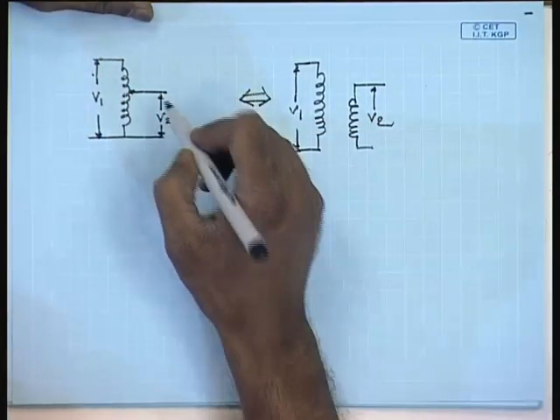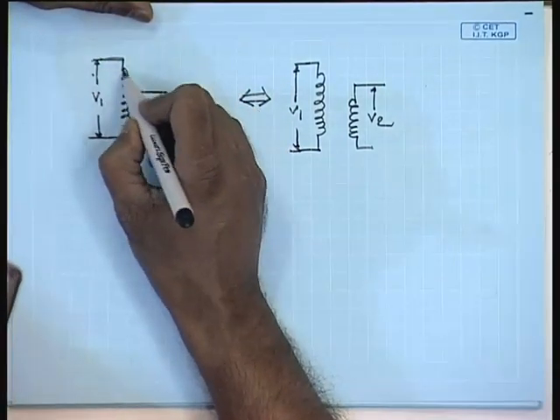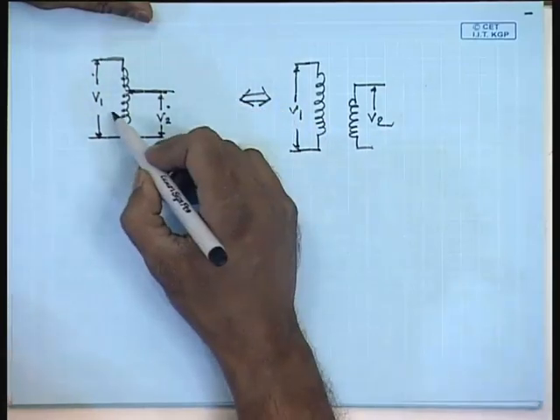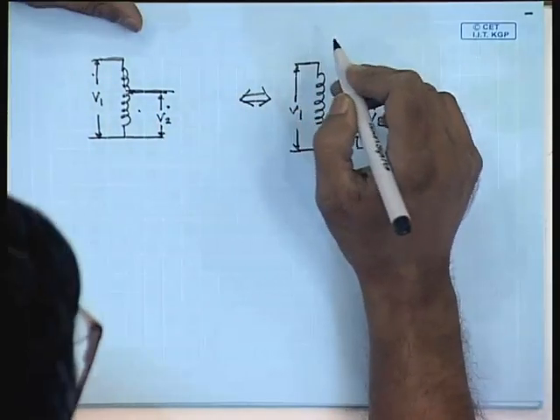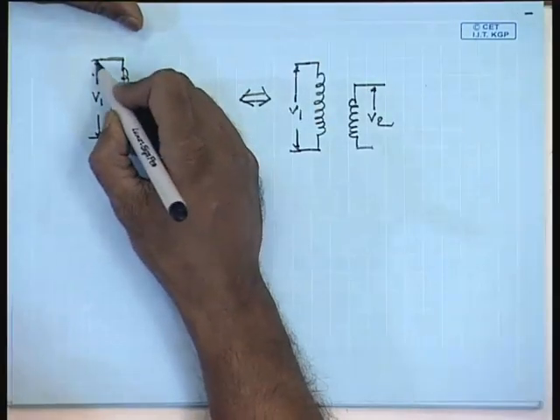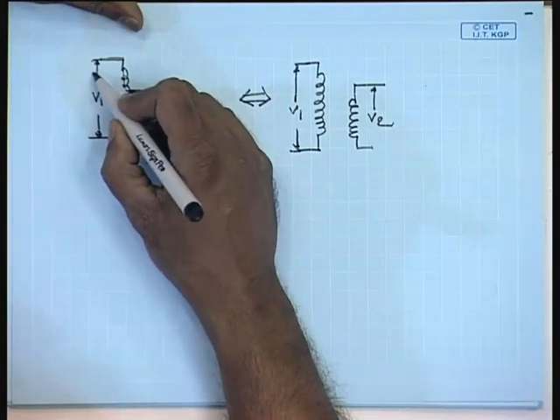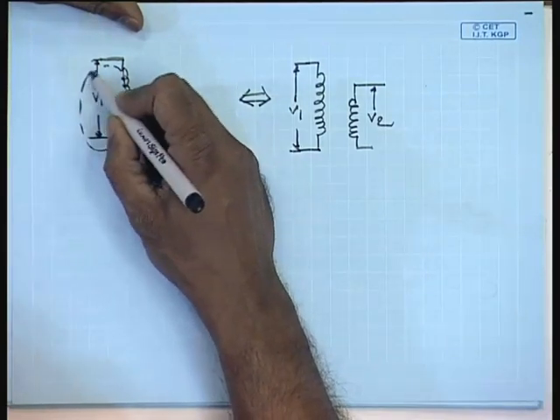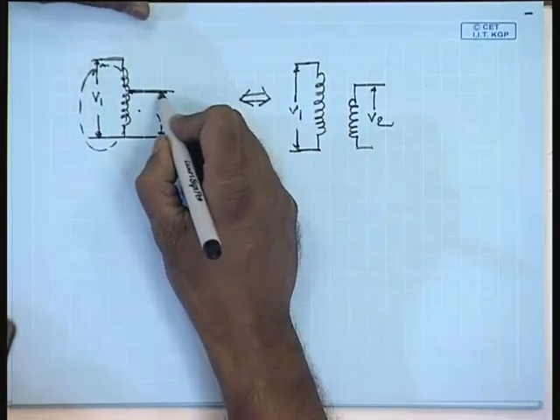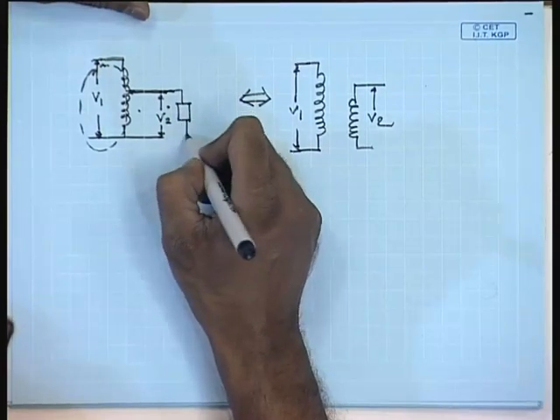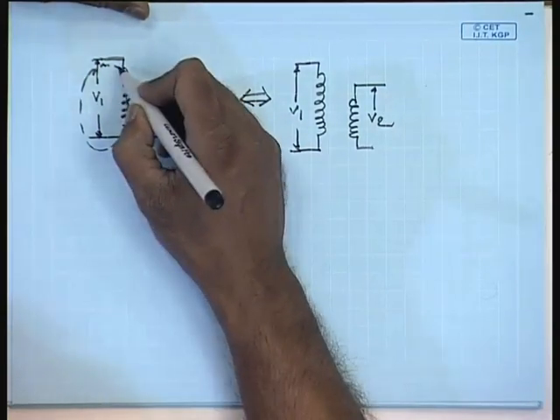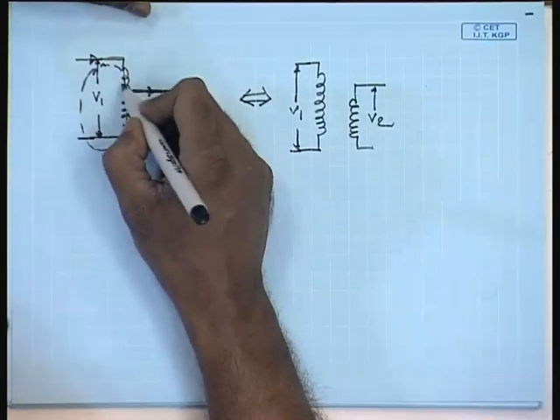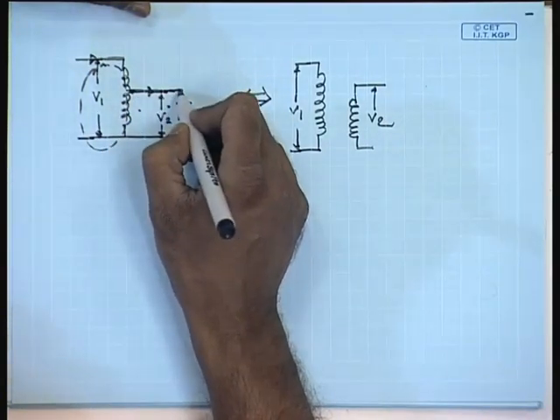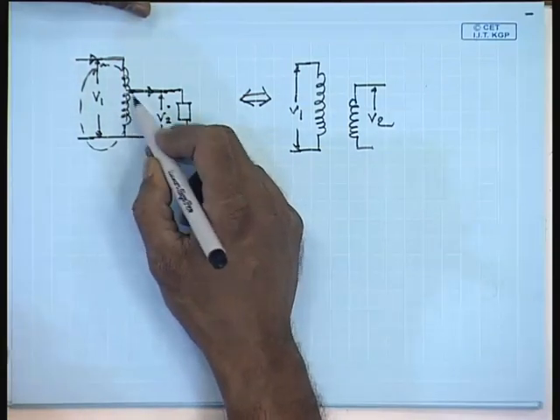the power transfer from input to output in this case occurs not only by the conductive path like this, but also by magnetic induction. By that we mean, when we apply a voltage here, a flux is produced which links both parts of the coil, and when a load is connected here, the current flowing through the load tries to change the flux. As a result, a reflection current is drawn from the primary side. A part of the power is transferred by the conductive path, but a part is transferred by the inductive part as well.